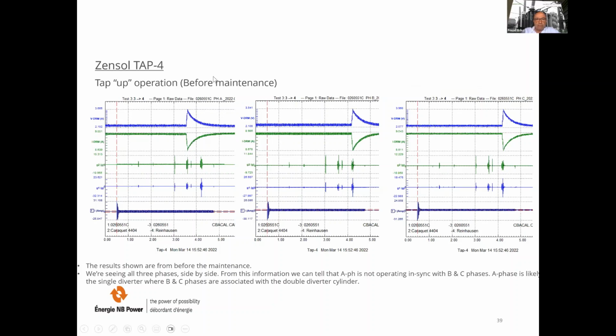So, tap up operation before maintenance. The results shown are from before the maintenance. We see all 3 phases side by side: phase A, B, and C. From this information, we can tell that A phase is not operating in synchronization with B and C phase. A phase is likely the single diverter, whereas B and C phases are associated with the double diverter cylinder. So here, I would like you to notice the DRM and these impacts. This is for B, and this is for C. And when you see the A in comparison, you can see the transition is happening on this impact. So there is something which is not correct.